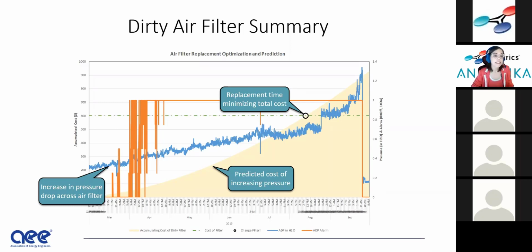But so you might replace this fan right away. Oh my gosh, it's an alarm now. It's been an alarm constant now in April. Or you might say in a preventative maintenance program, you know what, I have this thing scheduled for a filter replacement in 2 months, along with these other 5 air filters. I'm going to wait, right? A preventative maintenance program would likely result in replacing that air filter. I always say fan filter. Replacing that air filter either too soon or too late, inevitably.